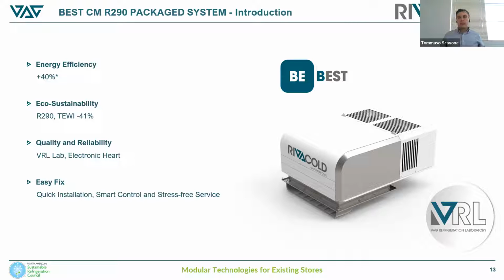In fact, we completely redesigned our historical rooftop monoblock with cutting-edge technology and the target to offer on the market the most advanced product in terms of energy efficiency that we will analyze deeply in the following slides. Eco-sustainability: the use of a natural refrigerant, propane in this case, that has a GWP equal to 3. And also, if used in an efficient system, as the one we developed for this monoblock, reduces both direct and indirect emissions, protecting our environment. So we calculated a reduction of the TEWI, or total equivalent warming impact, of up to 41%.